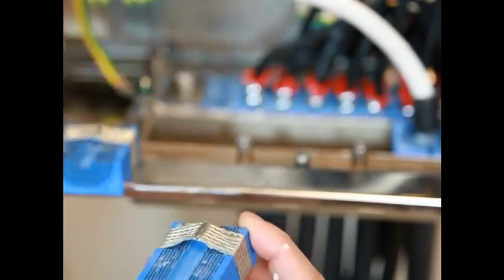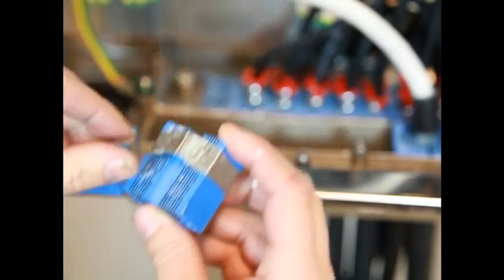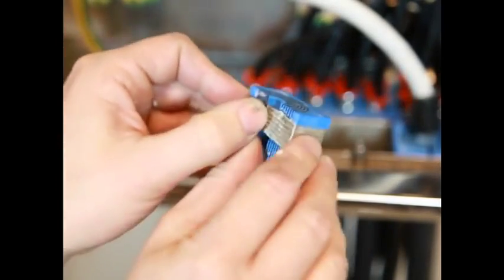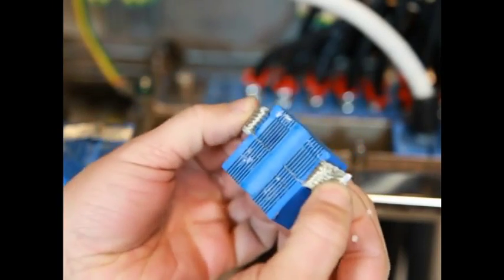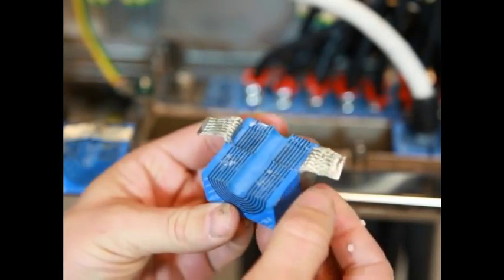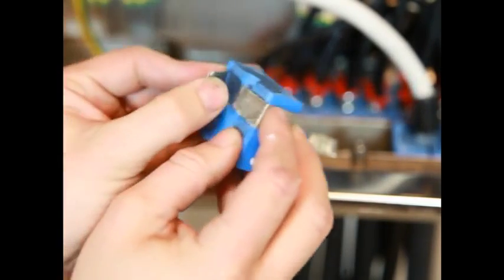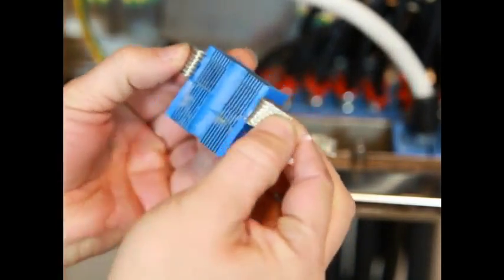Take out a spare module, remove the core, and fold out the braid. Adapt outer layers to the cable diameter and inner layers to the cable screen or armor. Fold the braid tightly inside the module. Make sure that there is a 0.1 to 1mm gap.